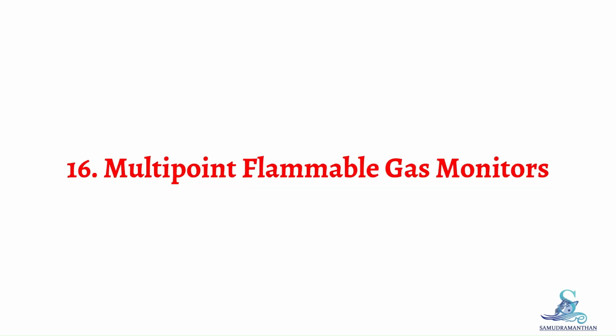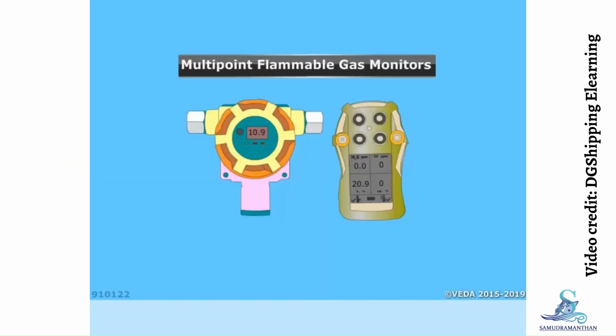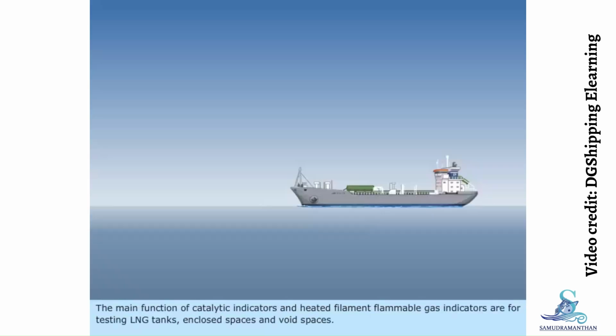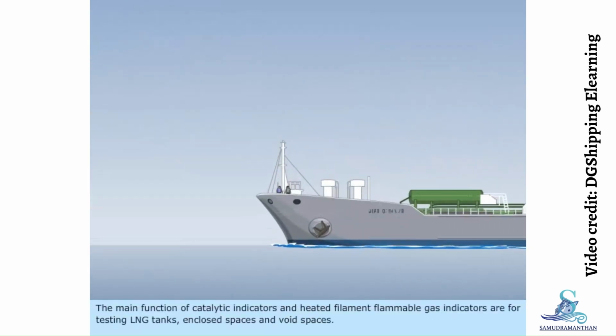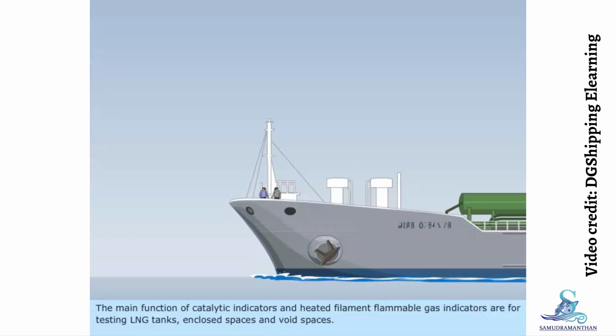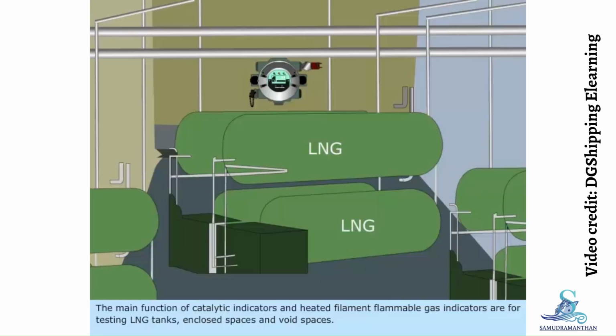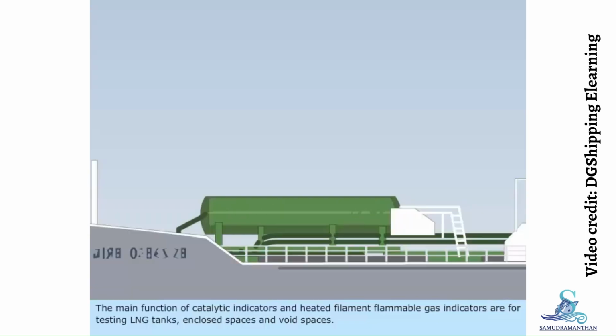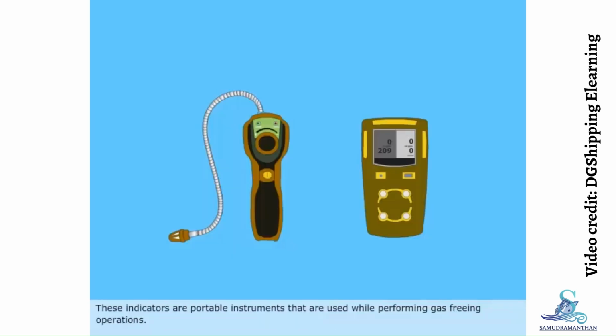Topic 16: Multipoint Flammable Gas Monitors. In this media, you will learn about multipoint flammable gas monitors. The main function of catalytic indicators and heated filament flammable gas indicators is for testing LNG tanks, enclosed spaces, and void spaces. These indicators are portable instruments that are used while performing gas-freeing operations.